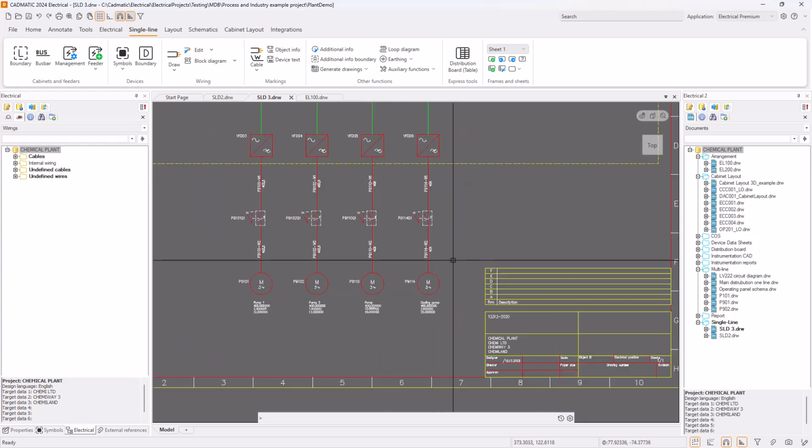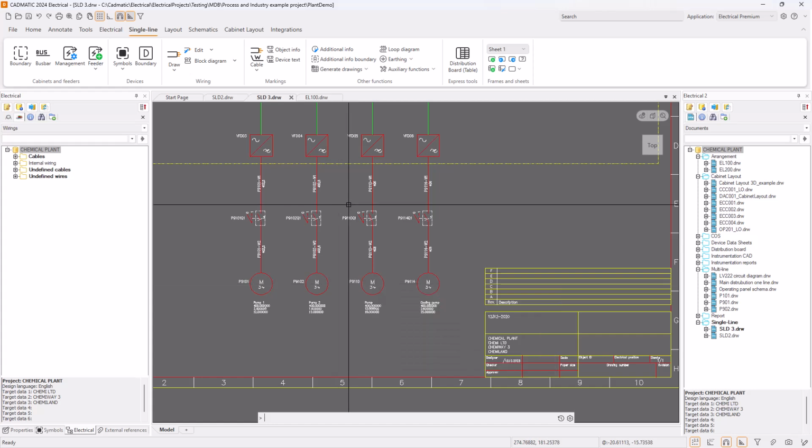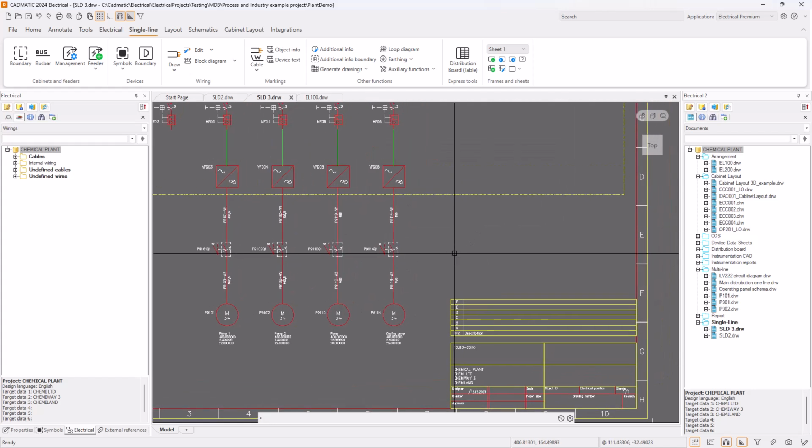Okay, so quite easily, by importing devices, copying existing ones, and just assigning these new devices to the correct position IDs in this project, you have connected this pump to the existing pump and created a couple of new cables and a couple of new devices in the electrical project. The workflow is very similar to traditional CAD software in that you can just copy things. It's important to understand that you copied cables and devices instead of just symbols.